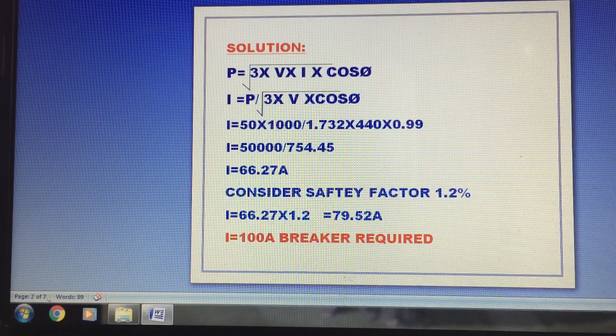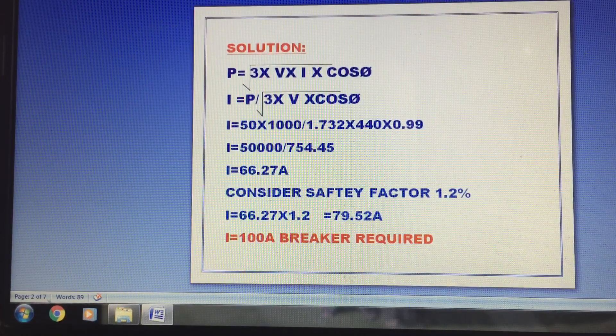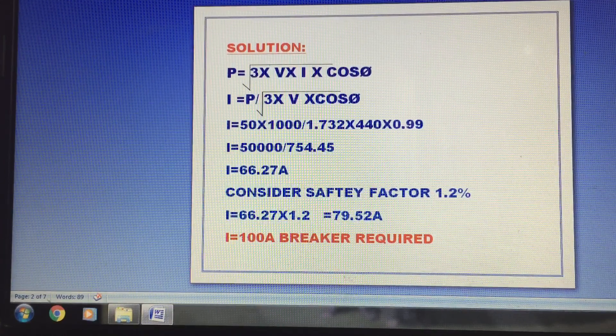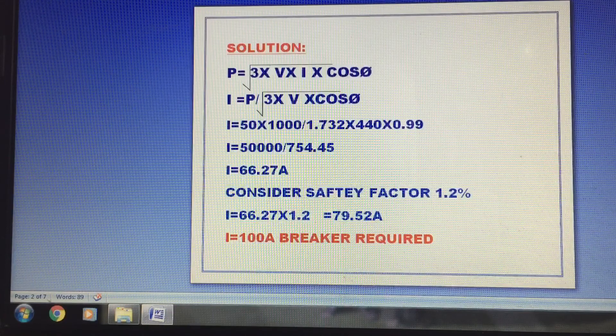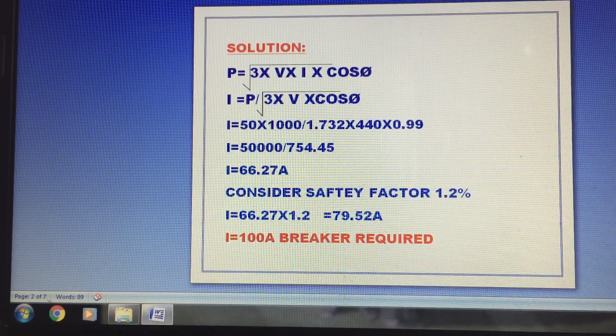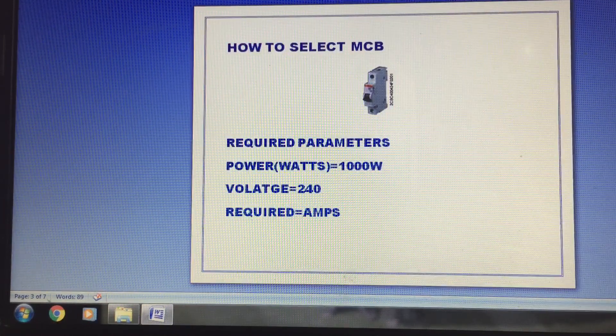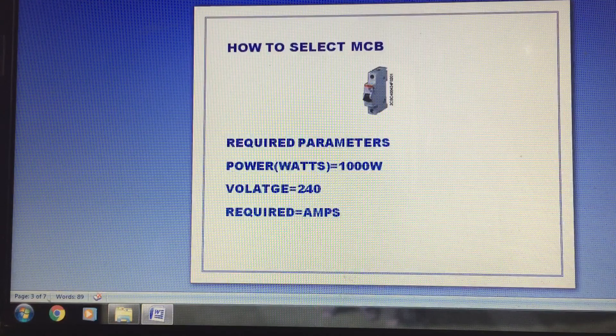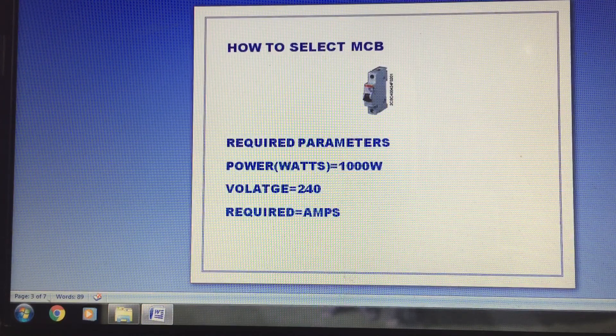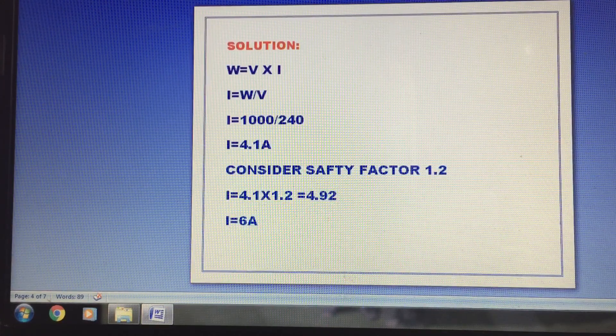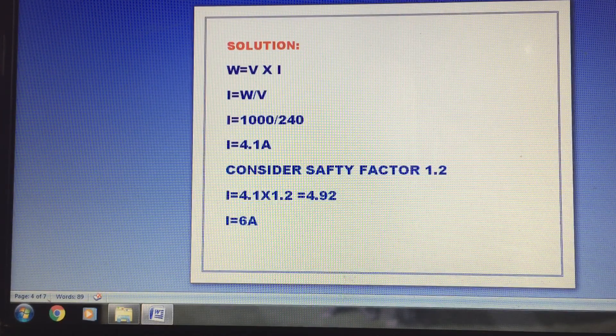Multiplying by the safety factor of 1.2, we get 79.52 amps. So the circuit breaker we need to design is approximately 80 amps. From what is available on the market, we select 100 amps. Now for a small application, we will do an MCB design. The parameters are 1000 watts, voltage is 240 volt. This is single phase, so the formula is W equals V times I.